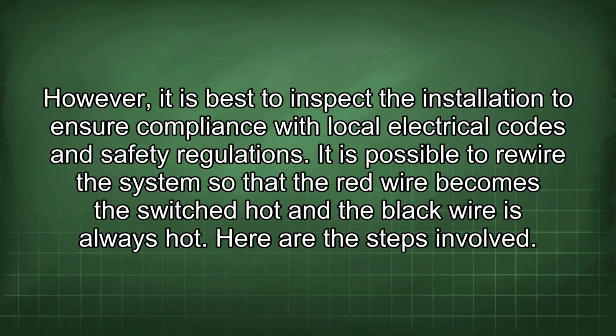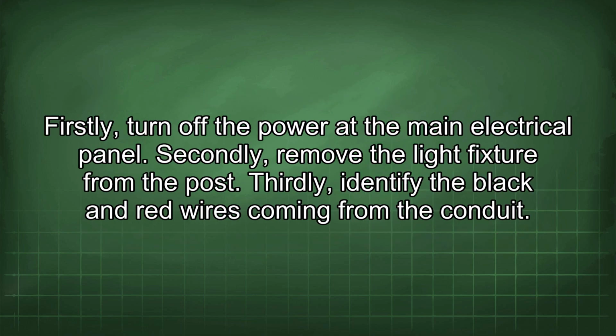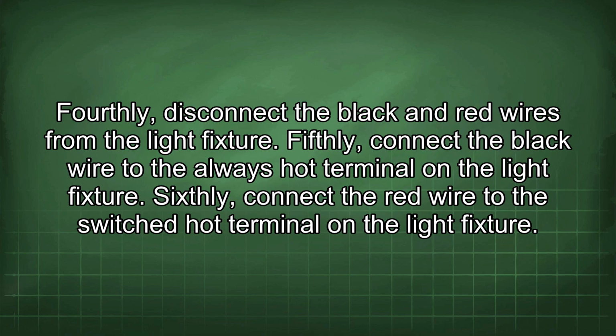It is possible to rewire the system so that the red wire becomes switched hot and the black wire is always hot. Here are the steps involved. Firstly, turn off the power at the main electrical panel. Secondly, remove the light fixture from the post. Thirdly, identify the black and red wires coming from the conduit. Fourthly, disconnect the black and red wires from the light fixture.